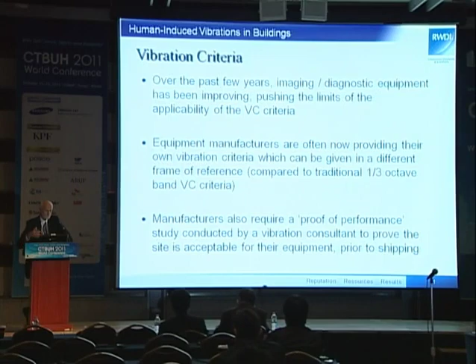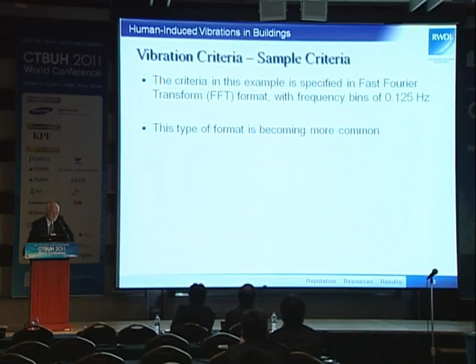Here's an example of one of the manufacturer's criteria curves as a function of frequency. This is now in a Fourier transform format, so it's a much narrower frequency band. The blue curve is what would be acceptable for the ambient floor vibration for this equipment if it has the standard equipment isolation system. If you're prepared to spend a bit more money and get an active isolation system or retrofit it, then you can relax the criteria to the upper curve, the mauve curve. That's just one example of trying to meet the manufacturer's requirements. In this example, it was specified in 0.125 hertz bandwidths, and this type of format for the criteria is becoming more common.